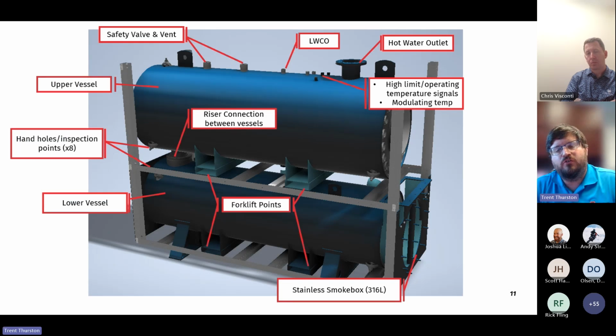Now, this is a picture of the boiler with the jacketing and insulation removed. One thing to note, these are 2 different vessels that bolt together. So we have bolt together at the riser connections and then at the front with the smoke boxes. So this can be separated, and each vessel has forklift points and lifting lugs on there. So if there is a tight installation location, this can fit through a standard width double door, assuming that middle bar is removed. Each boiler can be moved in separately and then reassembled inside the boiler room.